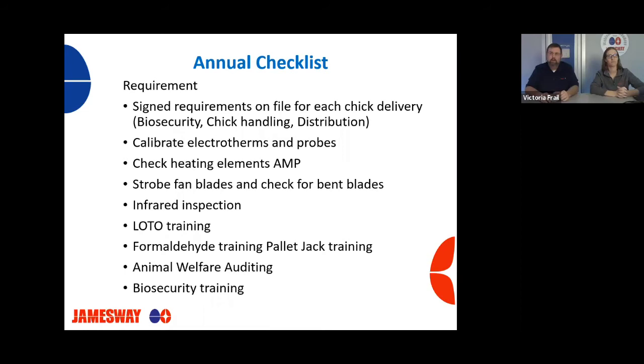Check the amp draw on your heating elements in your machines, your setters, and your hatchers. Strobe fan blades to check for bent blades, and you can also check RPMs to make sure you're getting the correct RPM so that the machine is operating properly. Right. An infrared inspection, typically most insurance companies require that now. They come in and take an infrared image of all your electrical distribution boxes, switch gears, transfer switches, breaker panels, any controls on machines, controls for automation. If you've never had one done, I would challenge you to do that. It's crucially important. I have been a victim of finding something, thankfully, and being able to repair it before a disaster happened.